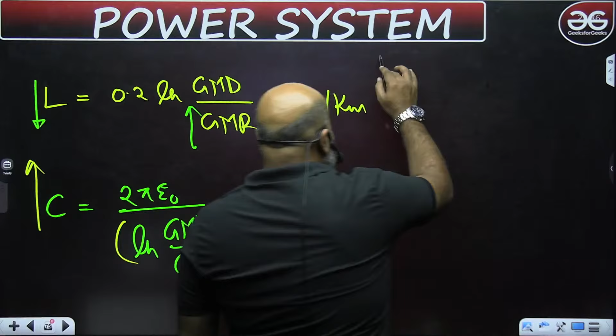What about the surge impedance, under root L by C? I am telling you the consequences of introducing the bundled conductor. L has reduced, C has increased, it means surge impedance has also reduced. What about surge impedance loading? It is V square upon ZC. Surge impedance is reduced, so it means surge impedance loading has increased.